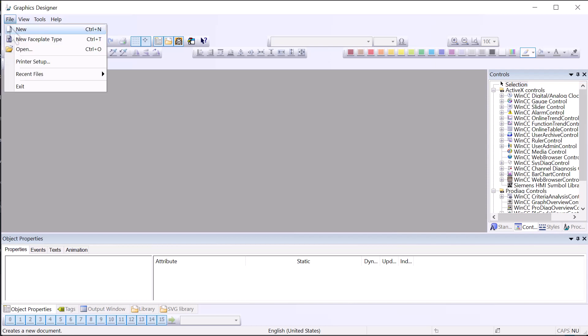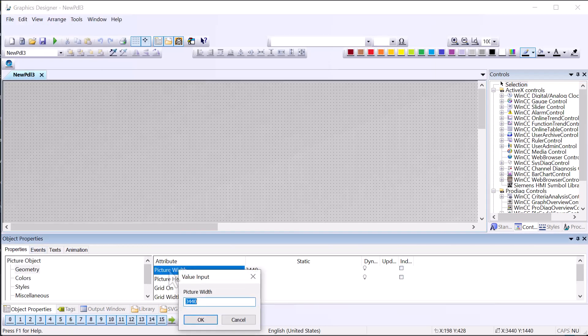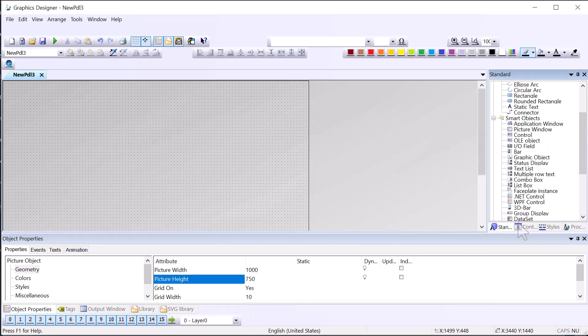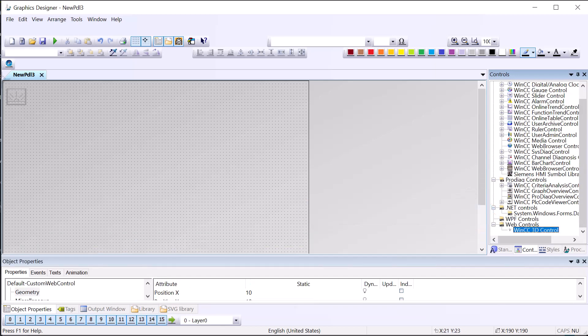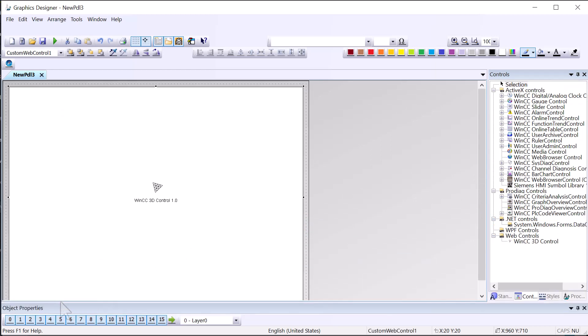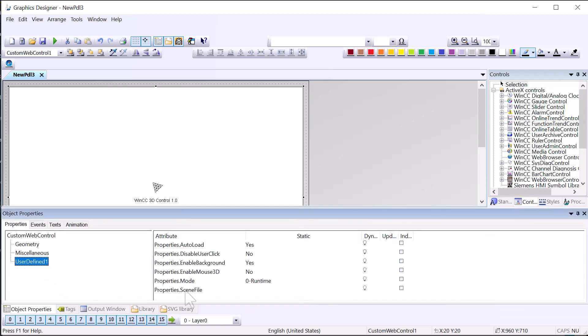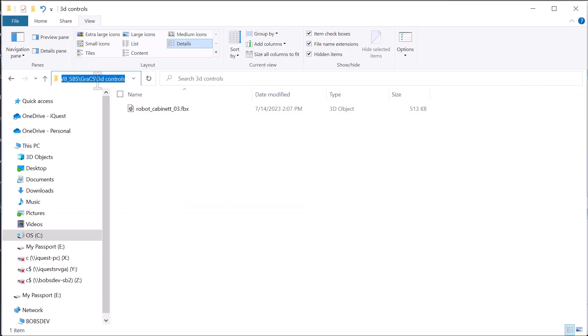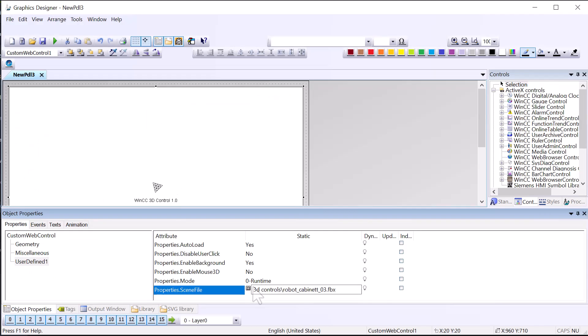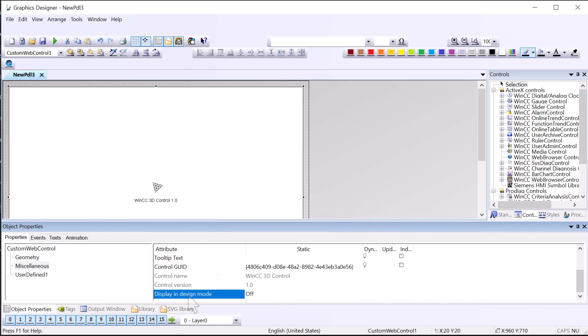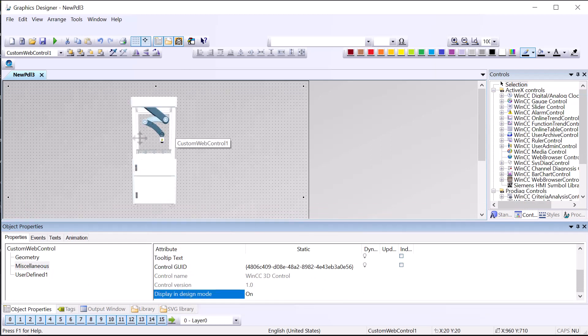Now we're going to go to Graphics Designer and create a new screen — I'll set it to 1000 by 750. On our controls palette, if you go to the bottom under web controls, you'll see WinCC 3D control. I'll position this how I want it. Under user defined properties, the scene file is where we tell the path to the file, and that's all relative to the GRACS folder. So all we need is '3D controls' and then the name of the file. I'll go to miscellaneous and turn on display in design mode to confirm it loads — and yes, that's definitely our file.